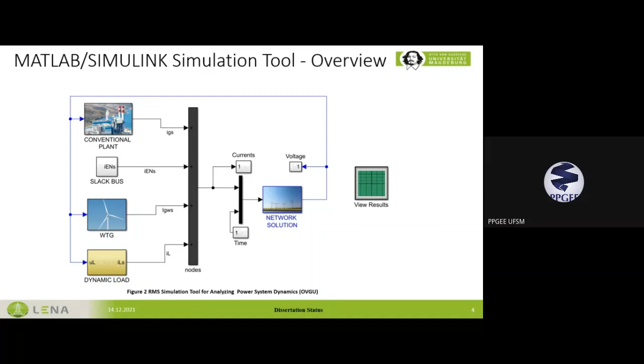I can show you with the 9-bus CHP system how the rate of change of frequency changes. With all synchronous generators, the rate of change of frequency is almost 0.05 per unit. If we introduce generators from wind energy, the lack of inertia increases, so the rate of frequency change increases because of the lack of inertia response from wind turbines.